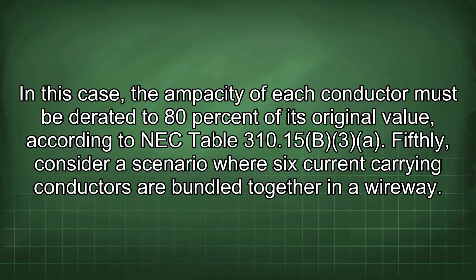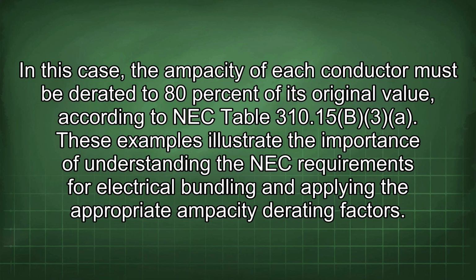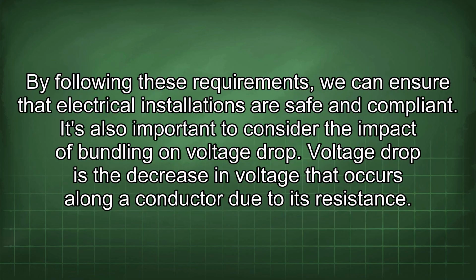Fifthly, consider a scenario where 6 current-carrying conductors are bundled together in a wireway. In this case, the ampacity of each conductor must be derated to 80% of its original value, according to NEC Table 310.15(B)(3)(a). These examples illustrate the importance of understanding the NEC requirements for electrical bundling and applying the appropriate ampacity derating factors. By following these requirements, we can ensure that electrical installations are safe and compliant.